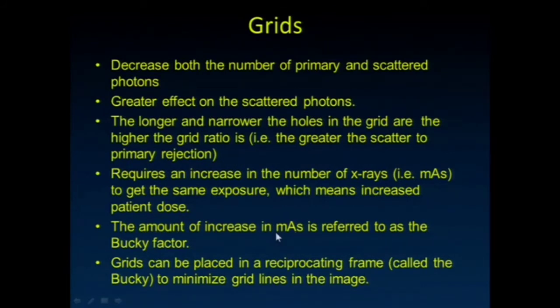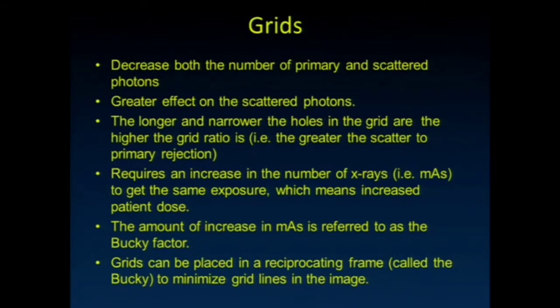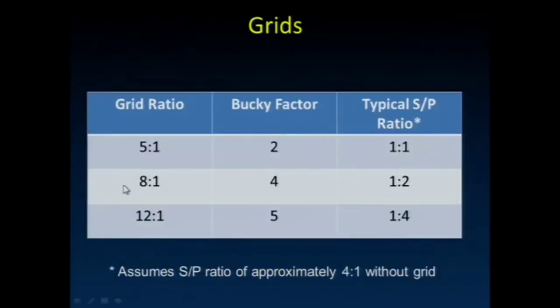You have to provide increased dose to the patient, and the amount of increase in mAs required is referred to as the Bucky factor. Grids are placed in a reciprocating frame—they vibrate just slightly, almost the diameter of the hole width, back and forth, so that you don't see the grid pattern on the radiograph.